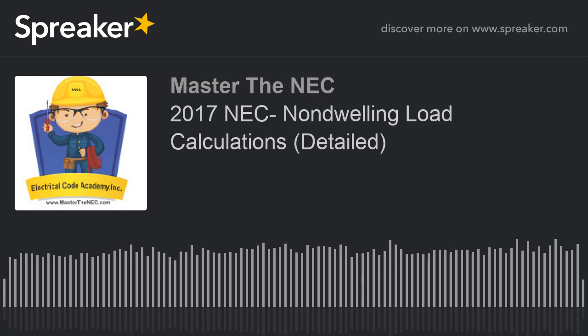We're going to be aware of the Notes 5 and all these other things. We're not going to worry about that. We're talking about all other electric cooking equipment, dishwasher, booster heaters, water heaters, all of these appliances that are, one, thermostatically controlled, or that is intermittently used as kitchen equipment. Okay, they're intermittent, it goes on and off. It's either thermostat controlled, clicks on and off, or they're designed to have intermittent use inside the kitchen area. Okay, so if we meet all of those things, and that's generally going to be most of the appliances that we're dealing with in kitchen equipment.